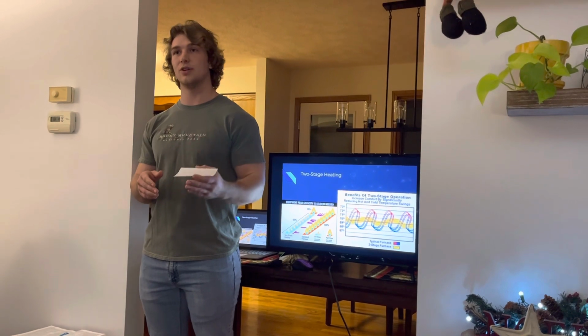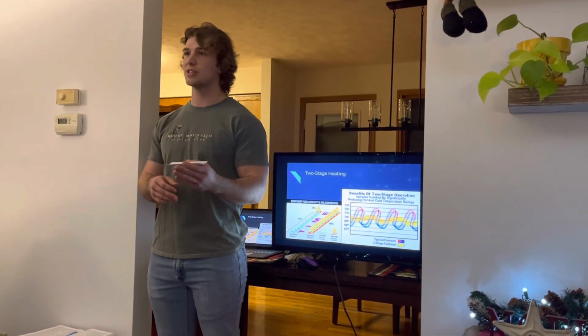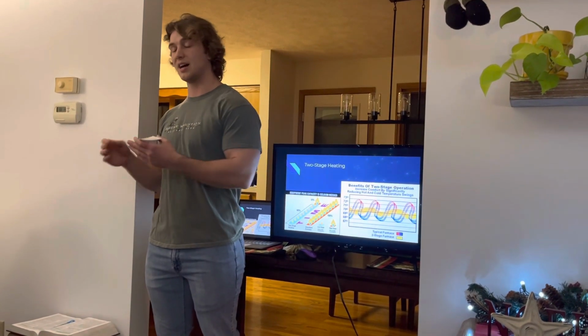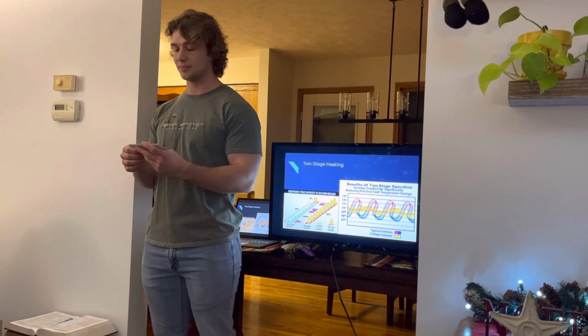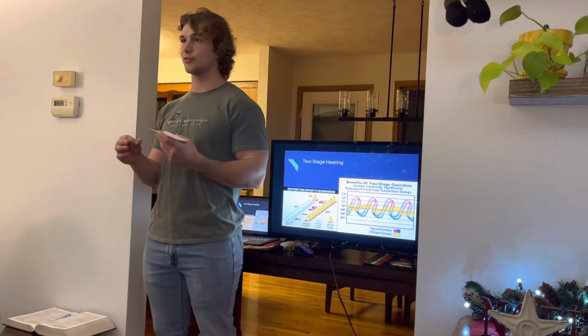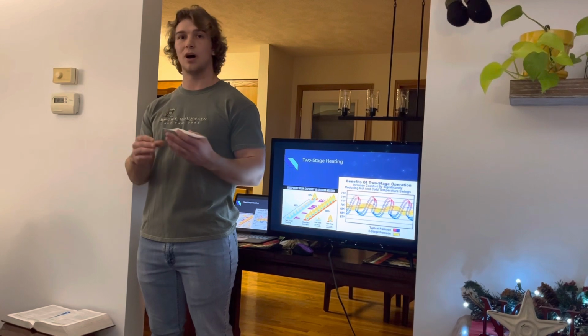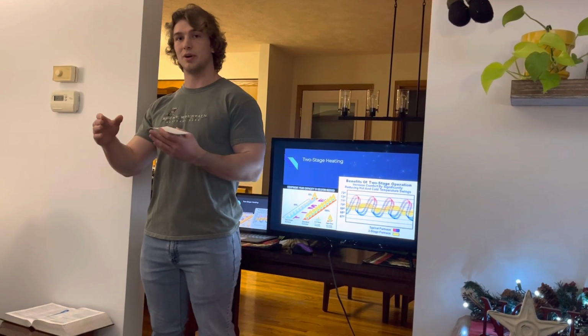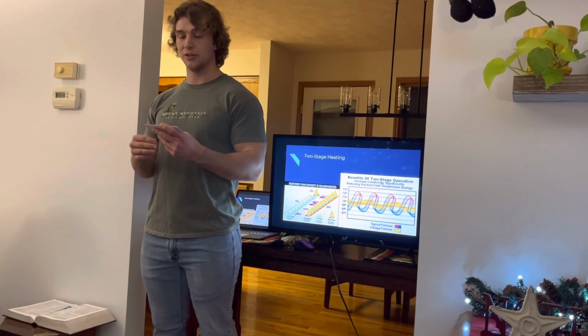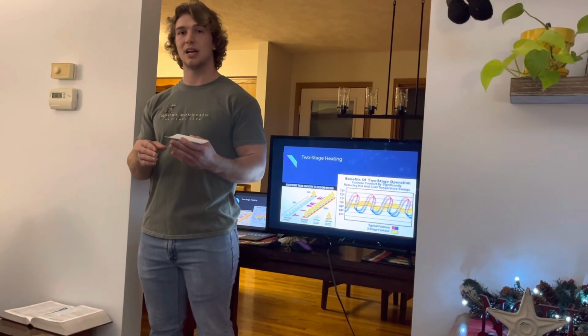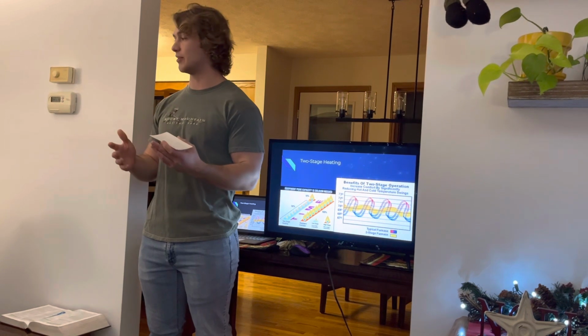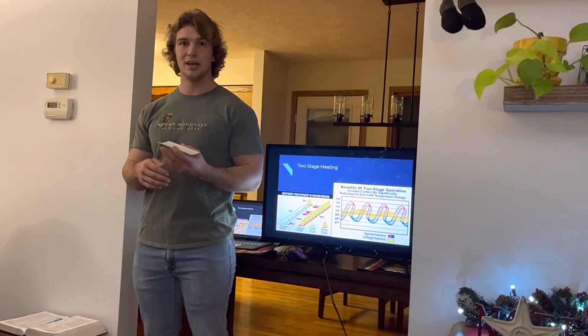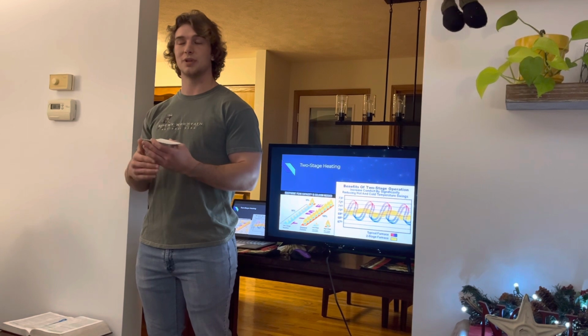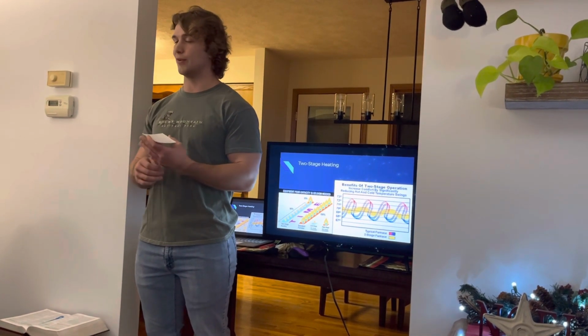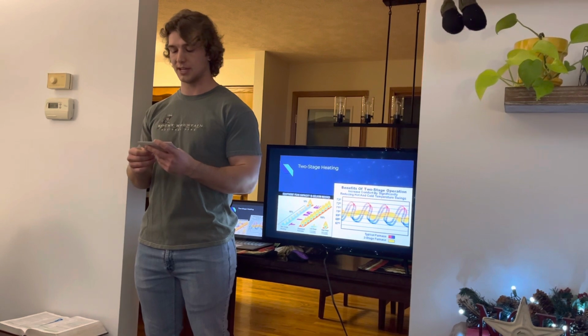This means your furnace will have a low stage and a high stage. In your low stage, your furnace will operate at about 60 to 65% of total capacity, and in high stage, it will operate at 100% capacity. Now, 80% of the time, your furnace will be able to satisfy the thermostat while on low stage, never having to bump up into high stage. But on those extreme cold days, after your furnace has run the allotted time in low stage, which could be around 5 minutes or so depending on the brand, it will then bump up into high stage and you'll receive 100% heat capacity, and it will allow for your furnace to satisfy the thermostat.